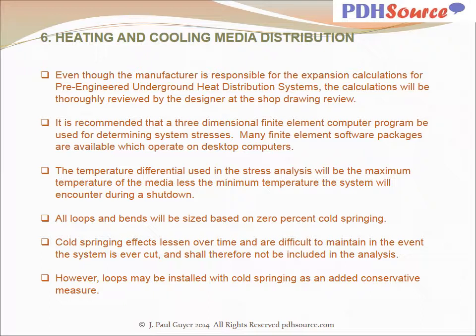It is recommended that a three-dimensional finite element computer program be used for determining system stresses. Many finite element software packages are available which operate on desktop computers. The temperature differential used in the stress analysis will be the maximum temperature of the media less the minimum temperature the system will encounter during a shutdown.